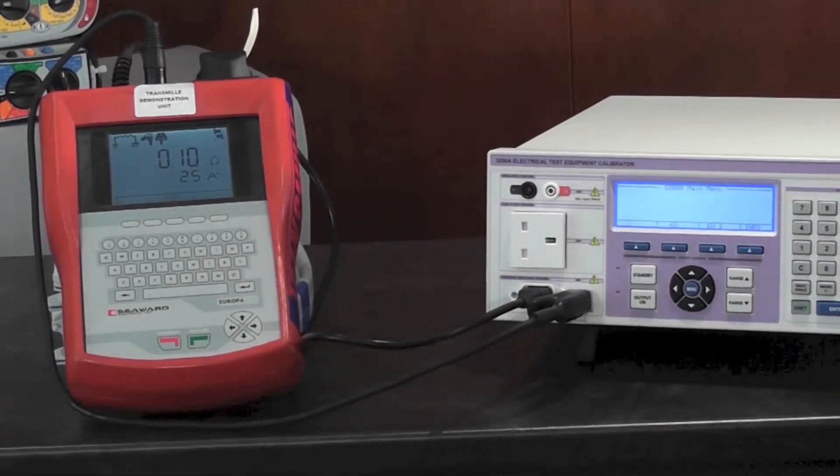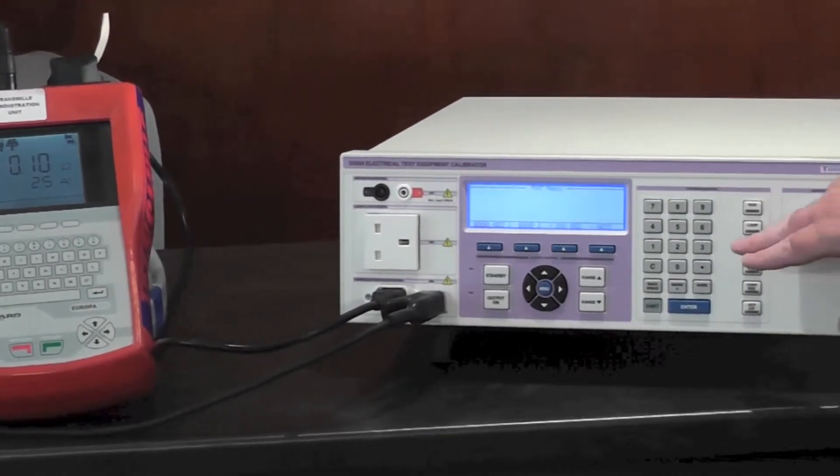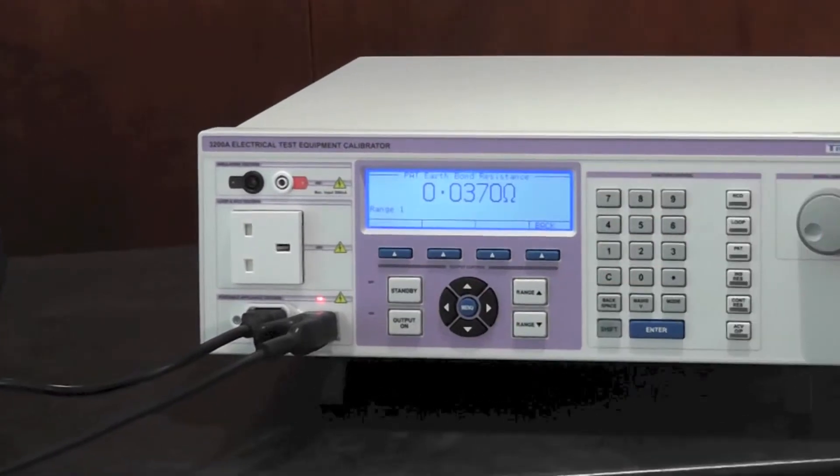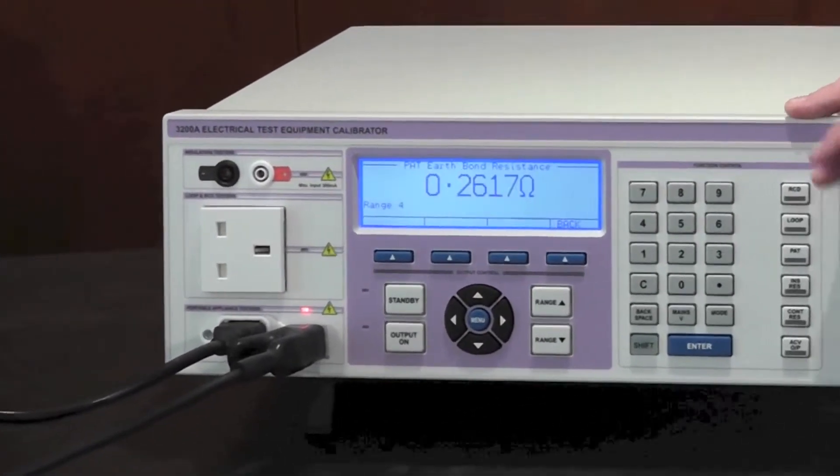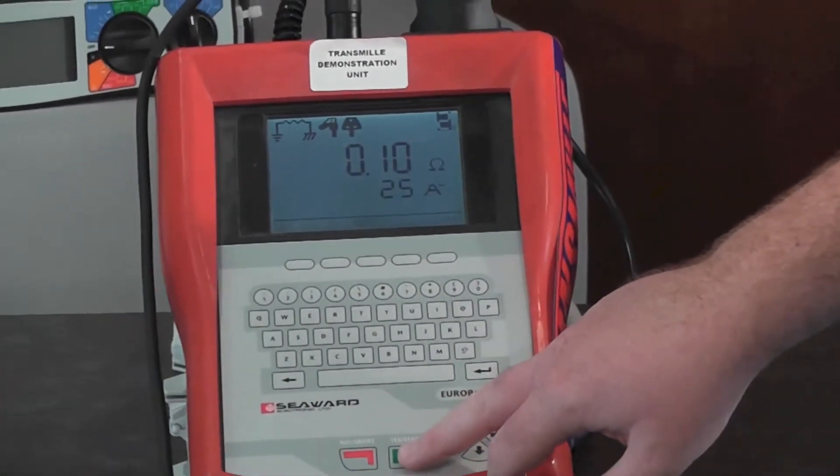I will now enter the PAT mode, select bond resistance as required, select the range using the digital control or the range up and down keys, and then press test on the tester.